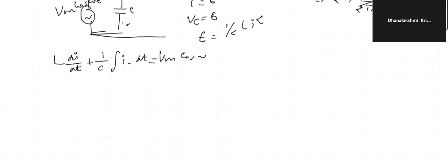In the transient immediately after the instant of arc extinction, the voltage across the capacitance Vc is the restriking voltage, which oscillates at the natural frequency. During this short period, the change in the power frequency term is very little and negligible.